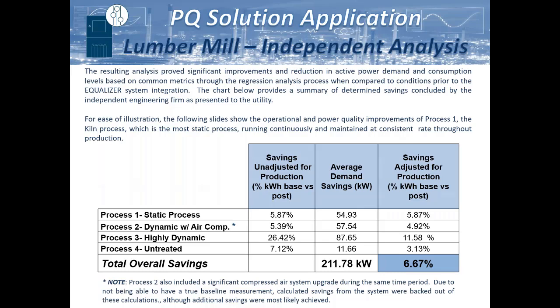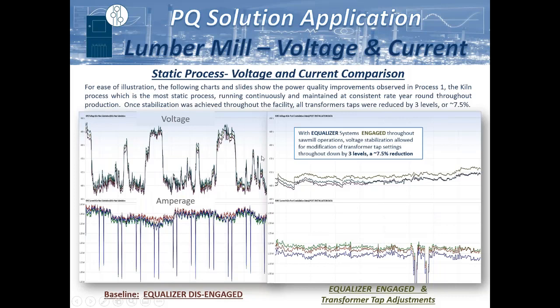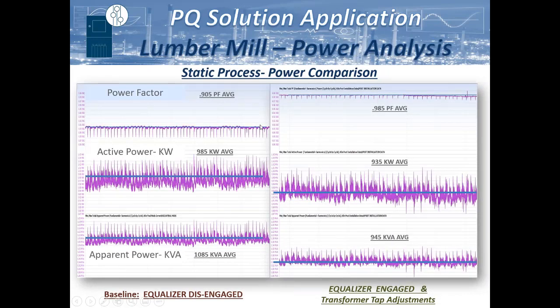The easiest thing to show for comparative purposes is that kiln, because it's a steady state process, so you can see the baseline. You could tell when the sawmill was not running versus when it was running, because you can see the impact on the voltage levels and also on the current levels. After we installed the equalizers, we were able to tap down all of the transformers on the facility by 3 levels. So now we maintain a steady voltage level and we lowered the current even further. This network was already running at a 0.90 power factor, and because of its steady state, it only needed an Activar. So now we got the power factor up to 0.985.